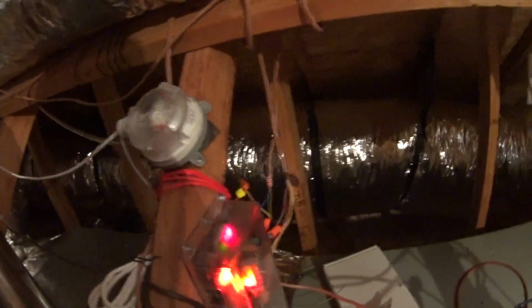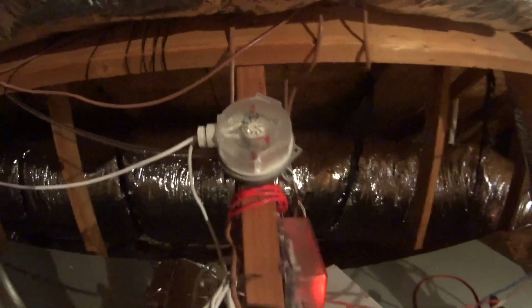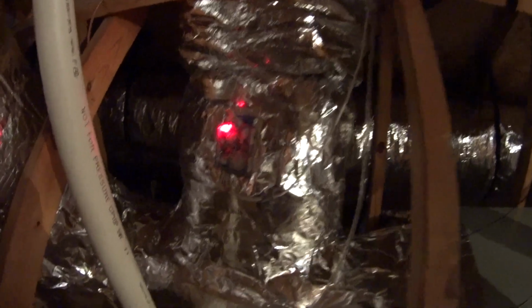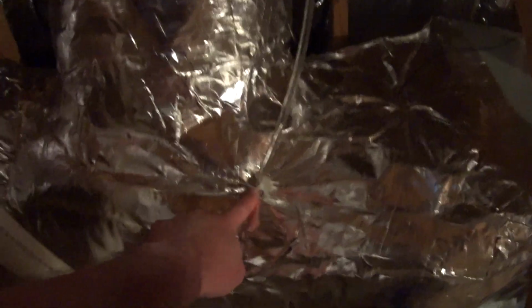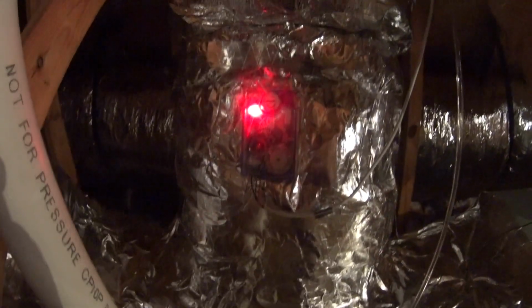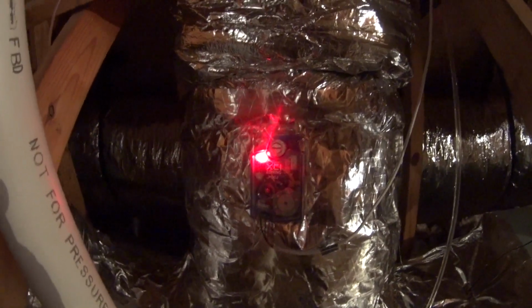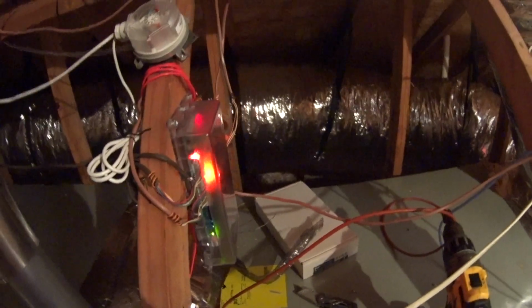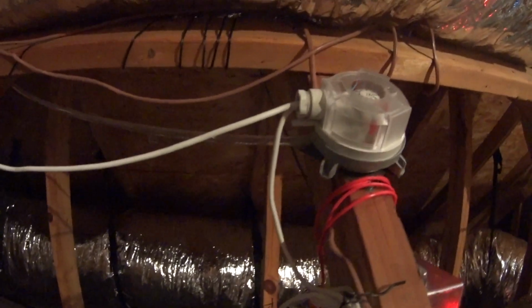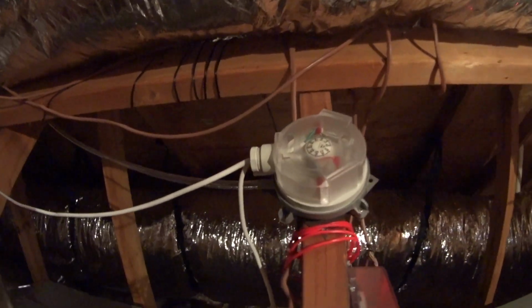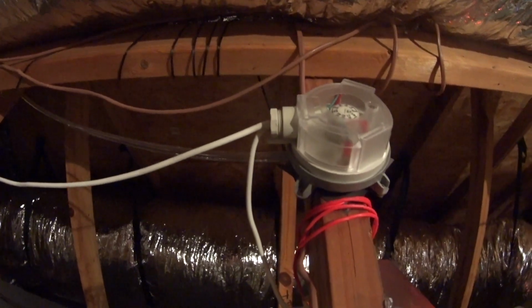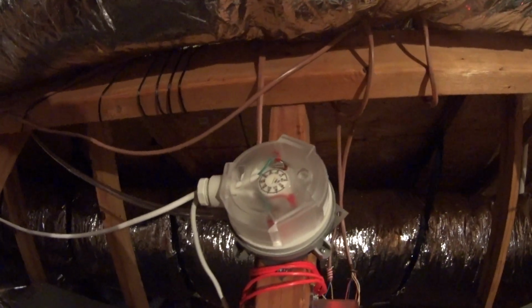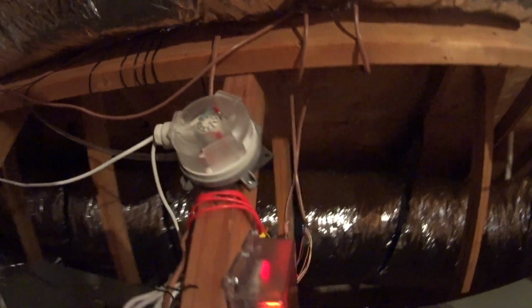And they're also using a powered bypass, which is governed on pressure. It powers closed based on static pressure, which it takes from different points on the ducting. So the red light indicates that that zone damper is closed for the bypass. And it looks like they're only taking high side pressure in, which you can set up either or, high or low side pressure to control the zone damper bypass.